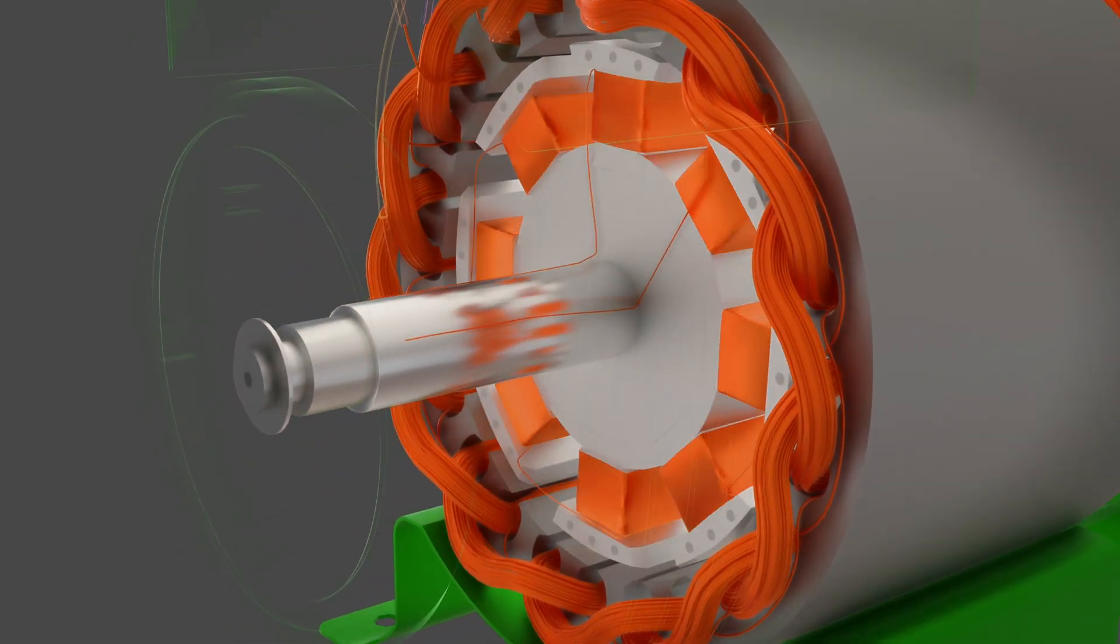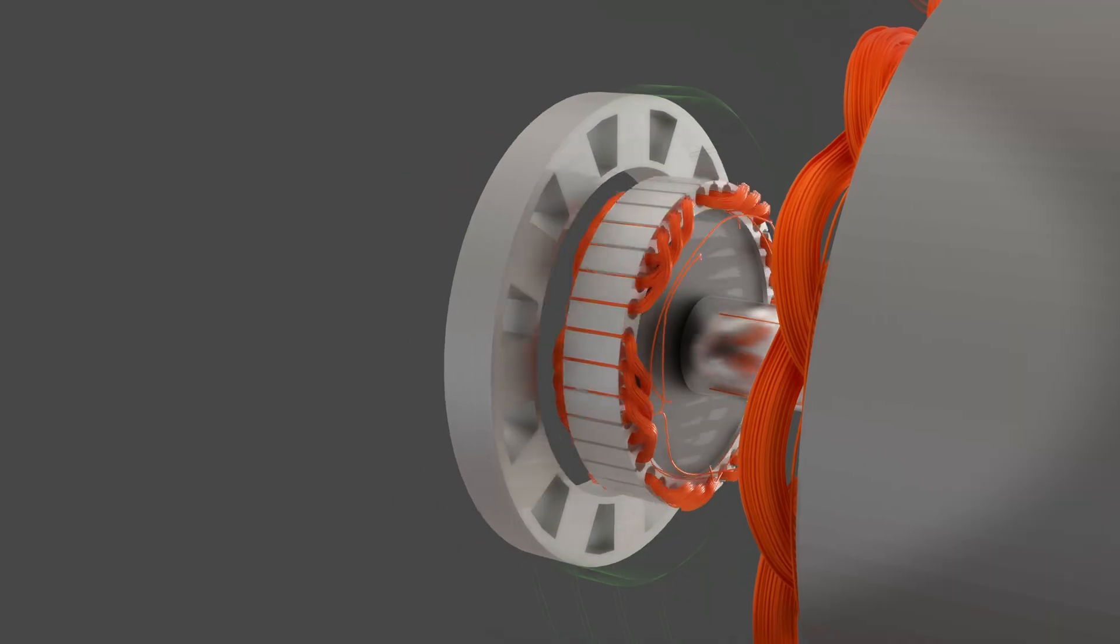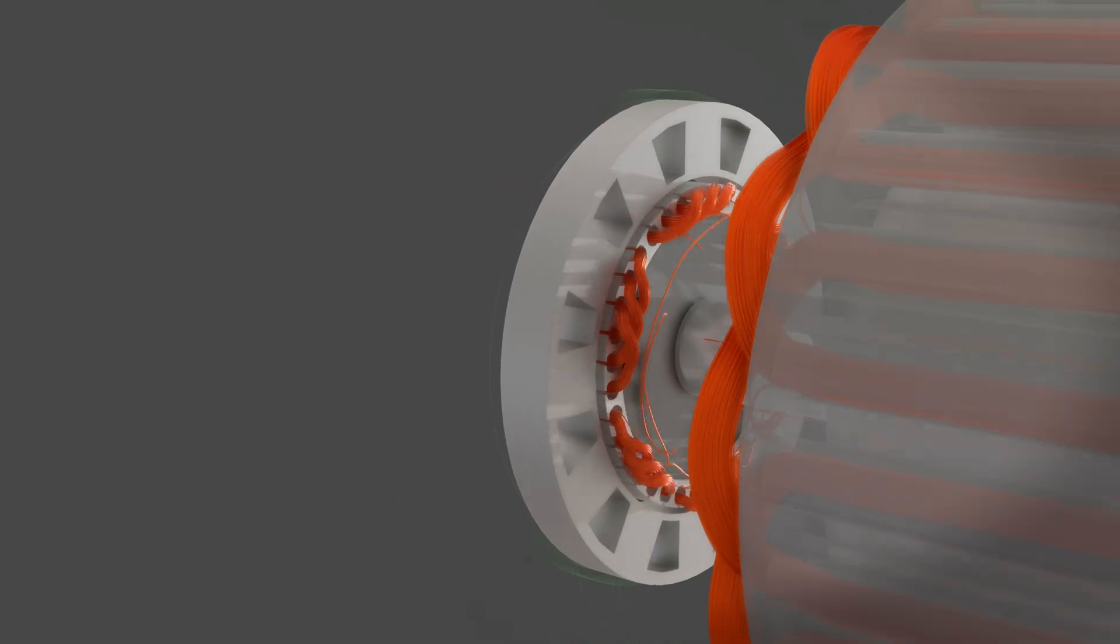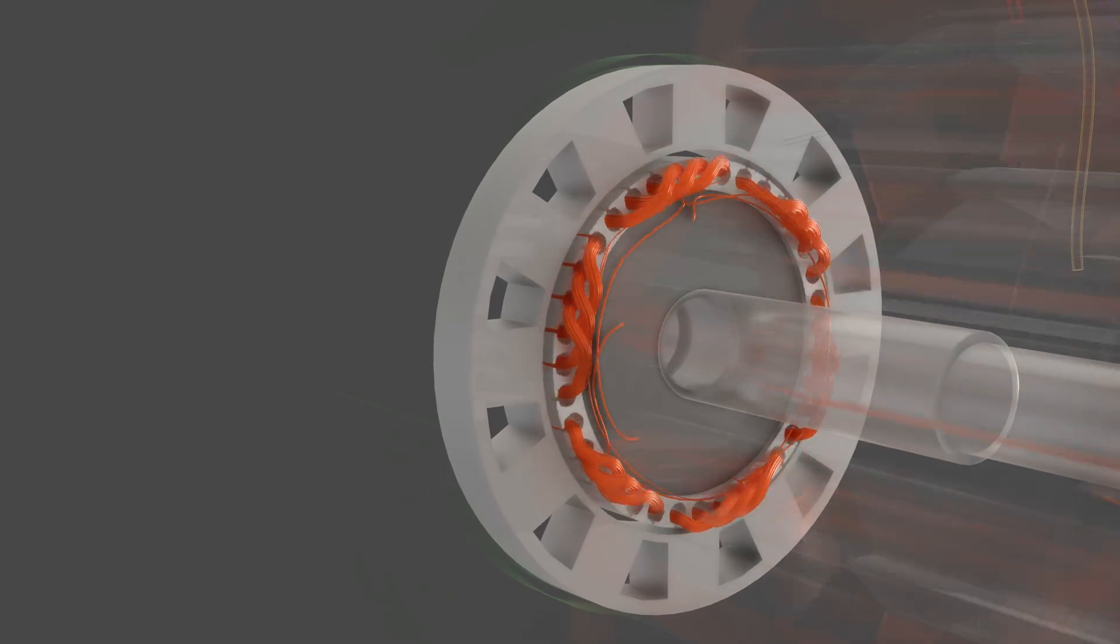Power is generated in windings mounted on the exciter rotor, and a separate exciter stator is fixed to the main case of the generator. DC power from the AVR is supplied to the exciter stator to generate magnetic field.